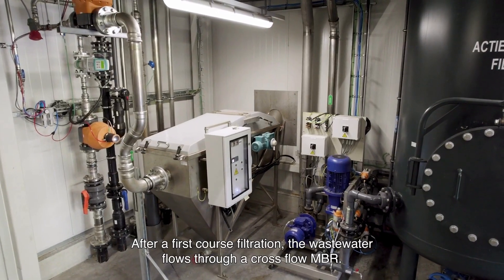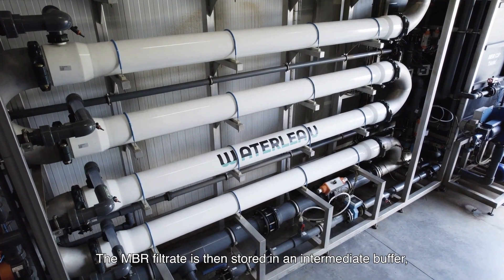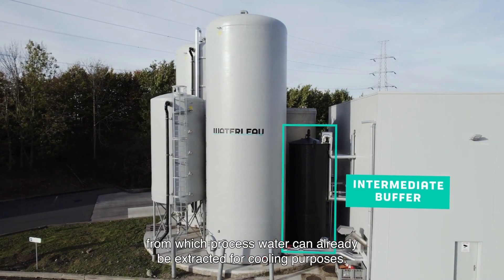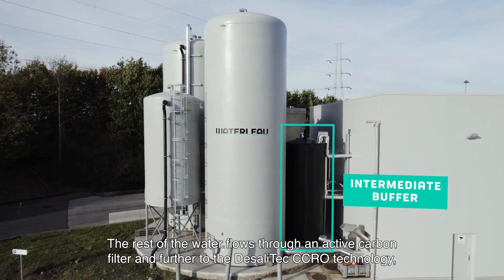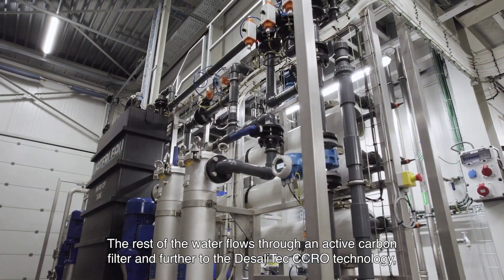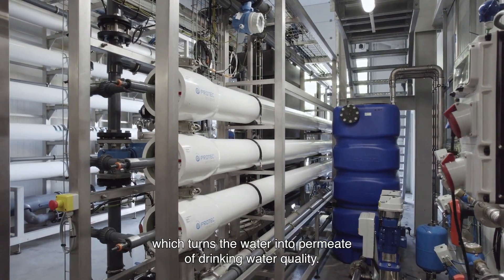After first coarse filtration, the wastewater flows through a cross flow MBR. The MBR filtrate is then stored in an intermediate buffer from which processed water can already be extracted for cooling purposes. The rest of the water flows through an active carbon filter and further to the DesaliTec CCRO technology, which turns the water into permeate of drinking water quality.